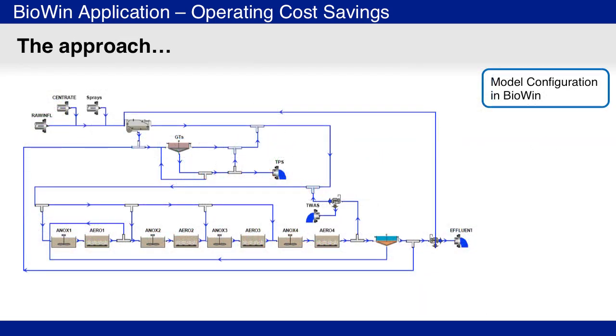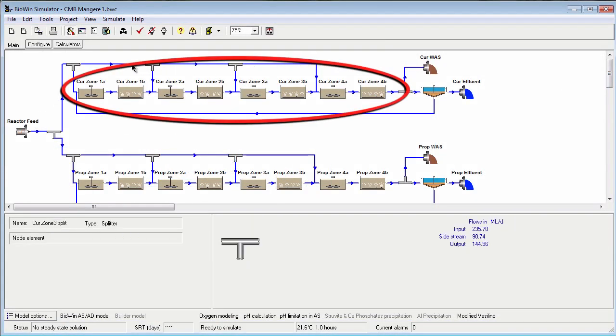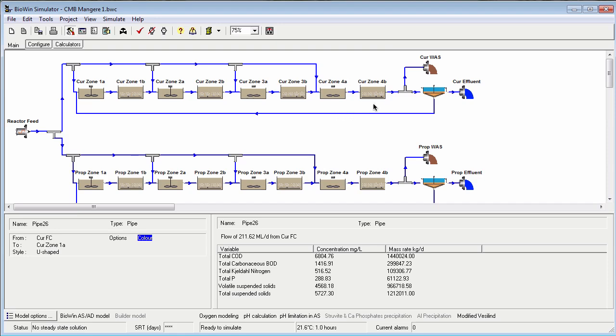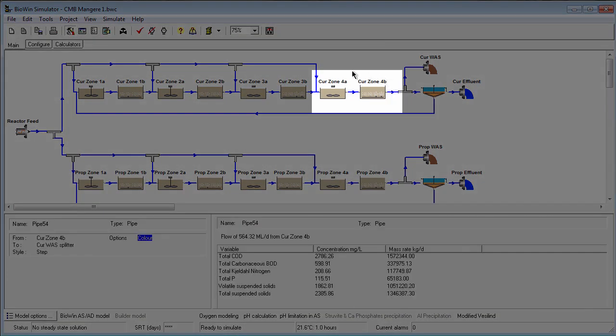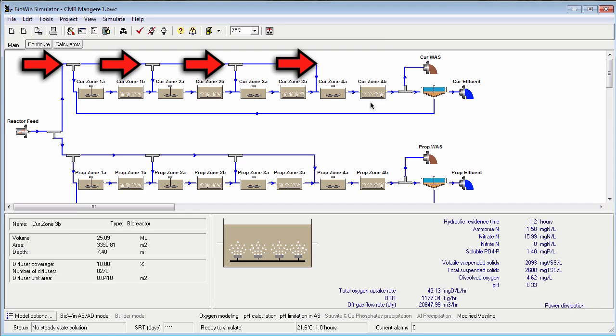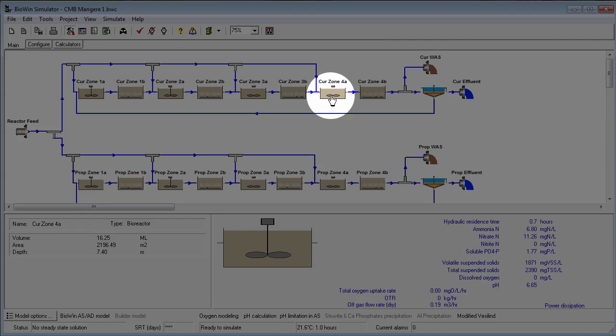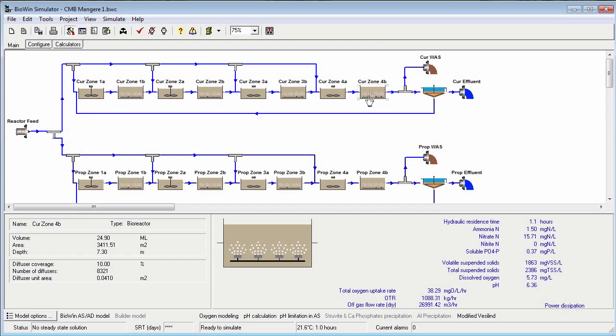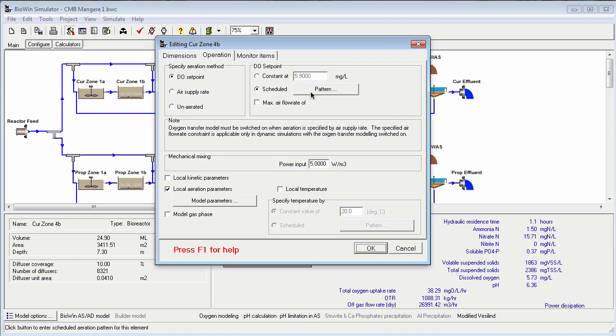The approach used was to set up a BioWin model of the treatment process. Each reactor clarifier was represented as a series of bioreactor elements to capture their plug flow nature, divided into four zones with each zone receiving a portion of the influent wastewater. Each of the four zones was split into anoxic and aerobic portions according to plant design, and dissolved oxygen set point schedules were input to the aerobic portions of the reactor clarifiers.